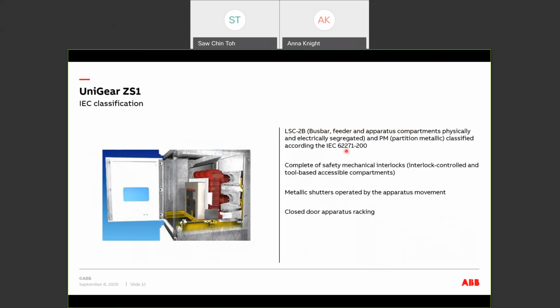Based on the IEC standards, UniGear panels are classified as LSC 2B. The busbar, cable, and circuit breaker compartments are physically and electrically segregated to provide the user with maximum service continuity. In other words, the operator can access the isolated circuit breaker compartment with the busbar and cable energized. These compartments are segregated by metallic sheets or shutters, and hence the class PM. The switchgear comes with safety mechanical interlocks as standard. The front side of the cubicle is classified as interlock controlled because access to the compartments containing the HV parts is controlled by the interlocks. The back of the cubicle is classified as tool-based accessible because it is possible to open the compartment with only a tool. Special procedures will need to be put in place.